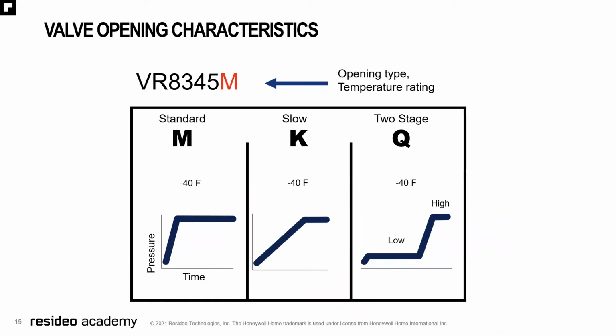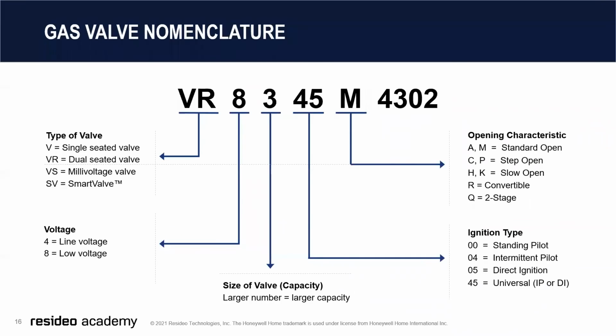The last designation after the family type tells you the opening and temperature rating. The standard, the slow, and the two-stage are all rated at -40, M being standard, K being slow, and Q being two-stage. Here's a breakdown of the gas valve nomenclature that we use. V stands for valve, VR stands for dual-seated valve, VS is for millivoltage valve, and SV is for smart valve.